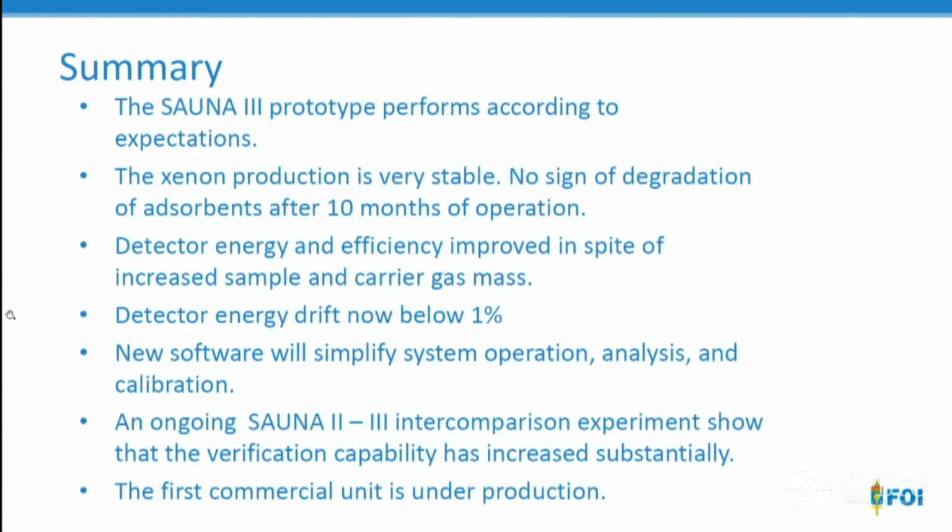To sum up, the SAUNA 3 prototype performs according to expectations. The xenon production is stable. We see no sign of degradation of adsorbents. The detector energy and efficiency improved, and the drift is below 1%. We have new software, and I think this comparison experiment showed that the verification capability has increased substantially. The first commercial unit is under production. Thank you very much.